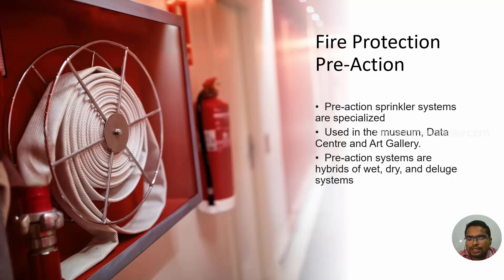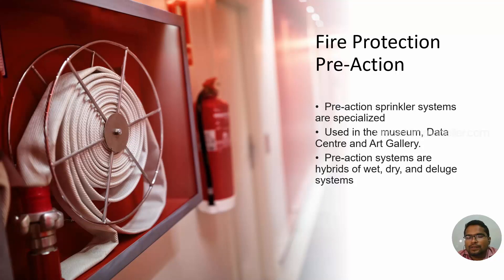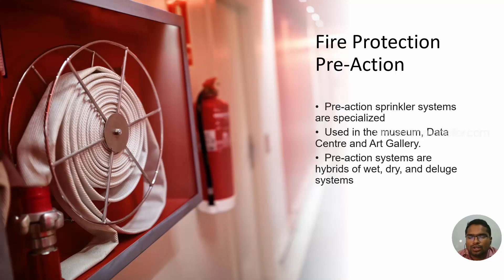Water will not come out unless conditions are confirmed. The valve will be opened, but the sprinkler will not have blasted — so if a sprinkler is accidentally broken, water will not come because it is a dry system and the valve will remain closed. The valve is controlled by the control panel, which also requires smoke to be detected by the smoke detector. Both actions — sprinkler activation and smoke detection — need to happen. Then the fire alarm will trigger and water will come out through the valve to whatever sprinkler has opened.